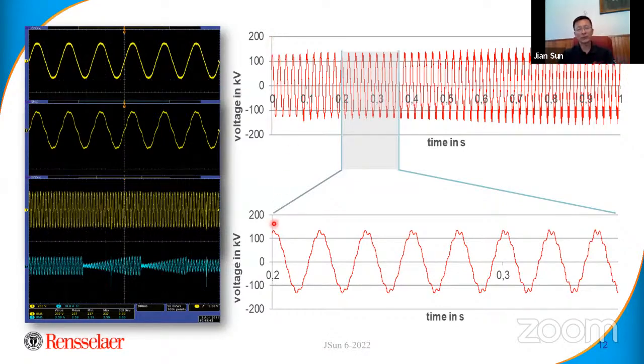If you zoom in, what you see is a growing harmonic. Initially it's relatively clean, but then a harmonic starts to appear and grows over several cycles to an unacceptable level. In the zoomed-in view you can see the harmonic, it's still small there, but it can grow to 20 or 30 percent, and that becomes a major problem.